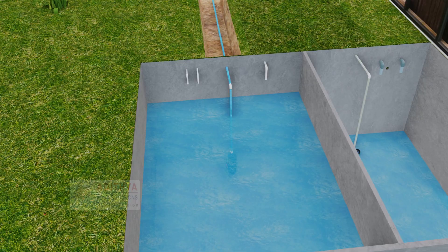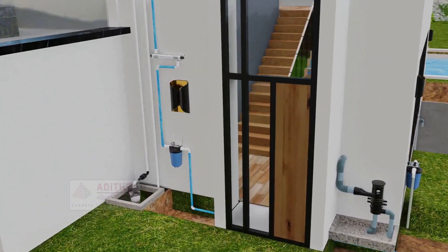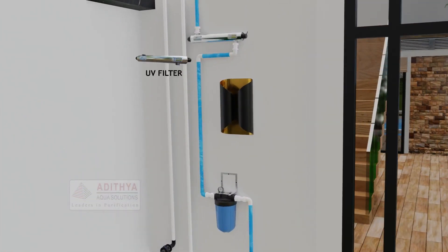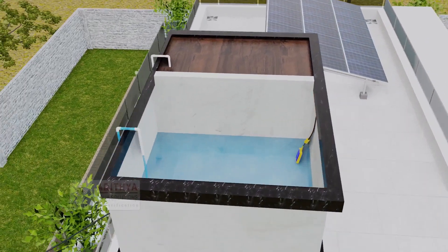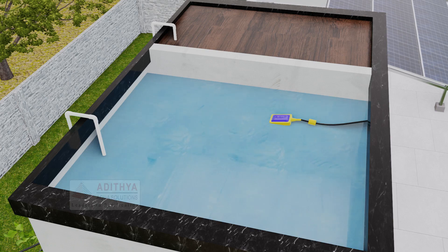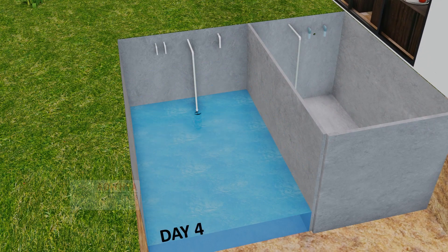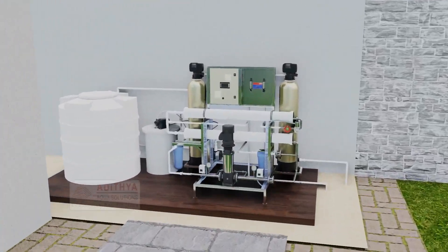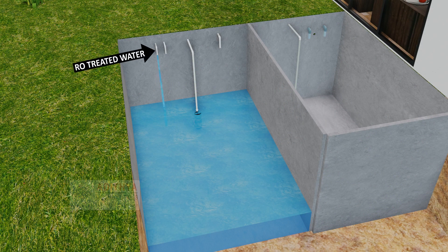Through the transfer pump in the supply sump, the purified water first goes through bag filtration and UV filtration, killing germs before being sent to the overhead tank. When the overhead tank fills, a float identifies it and stops the water filling. When the water in the supply sump reduces during water scarcity, the RO unit recognizes it and first initiates use of corporation water. When that too is unavailable, it purifies the borewell water and fills the supply sump.